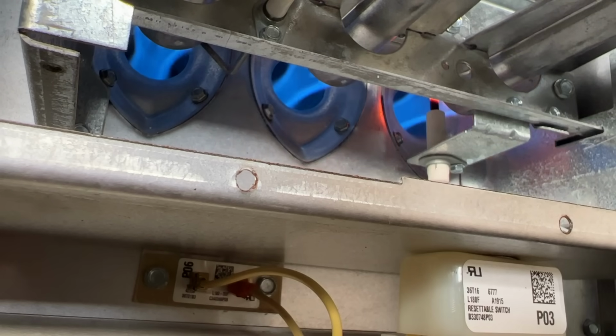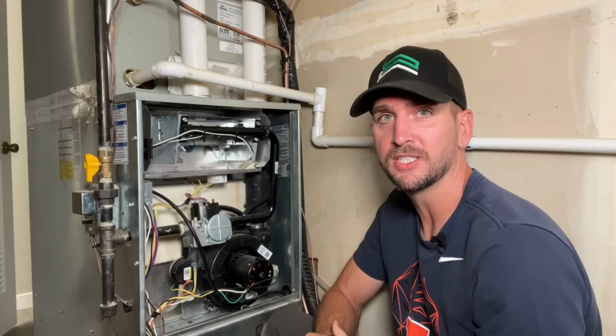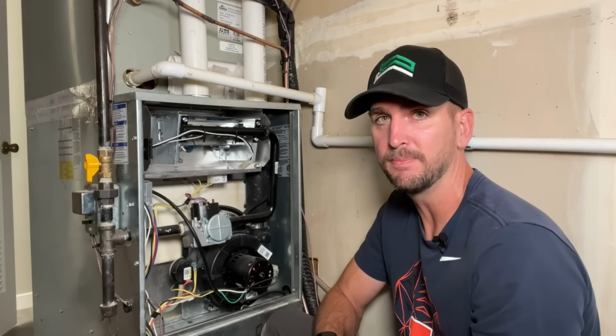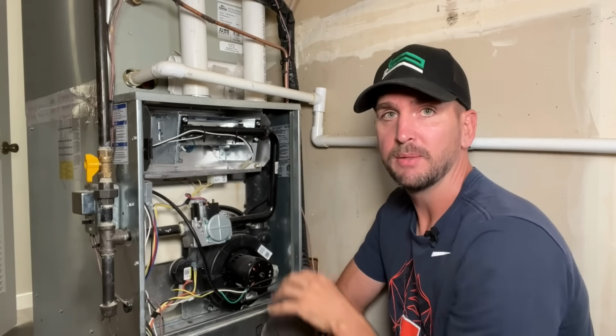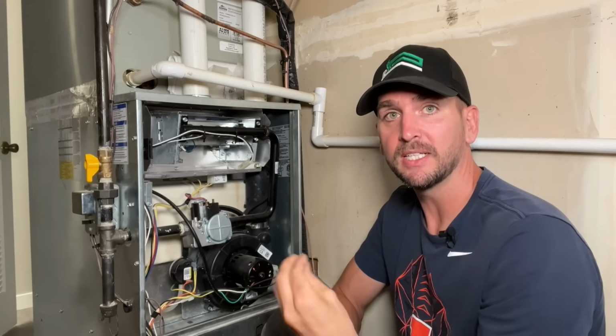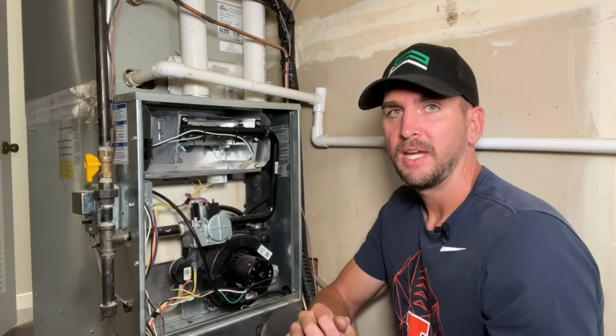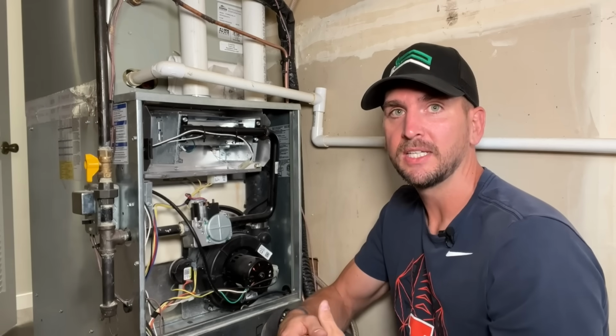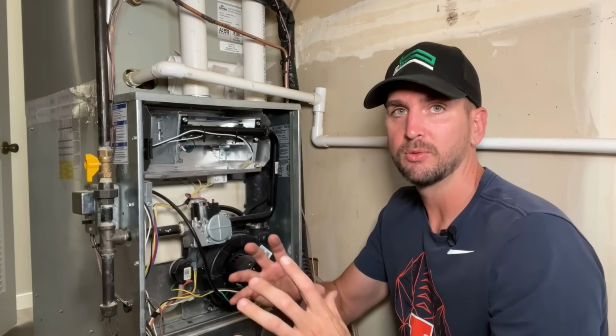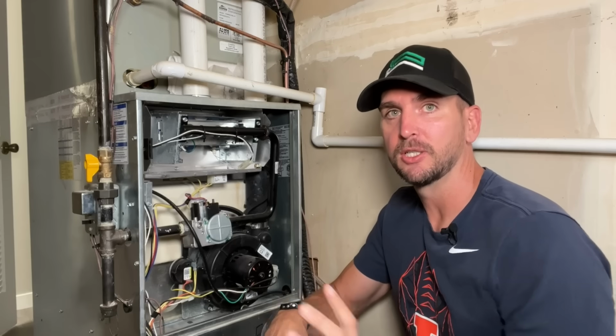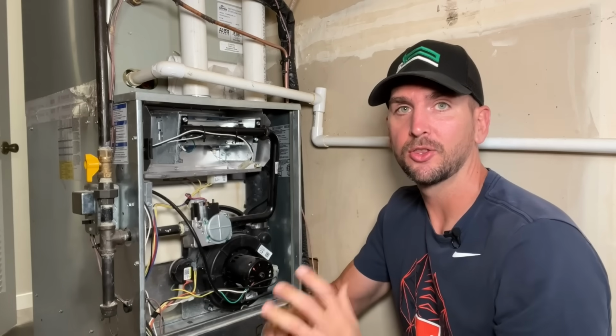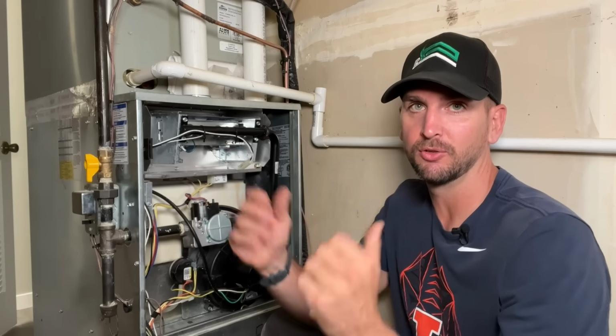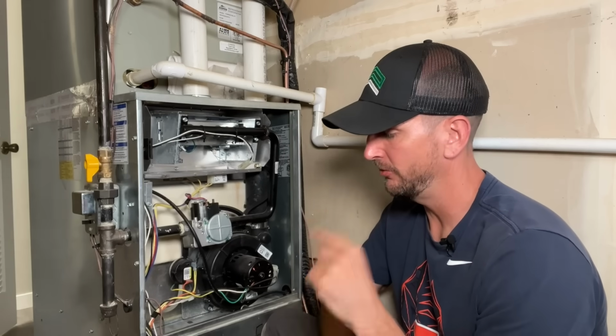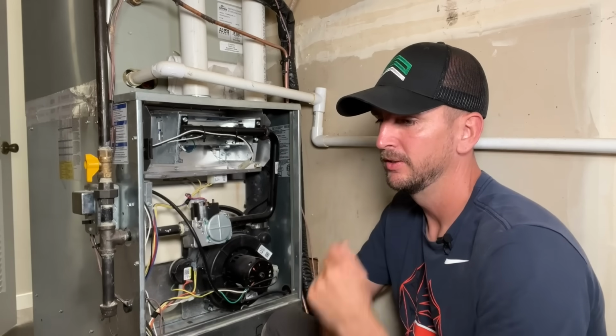Now step 5, you're having a flame detection sensor confirming the flame. And then once those flames are confirmed to be there and your heat exchanger starts to warm up, after about 30 or 45 seconds, your main blower fan will start up, and that's what's actually going to push that conditioned air through your ductworks and out of your vents. And we'll hear that blower fan come on here shortly.